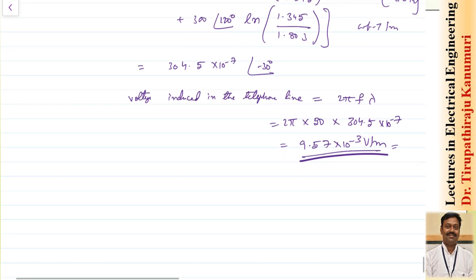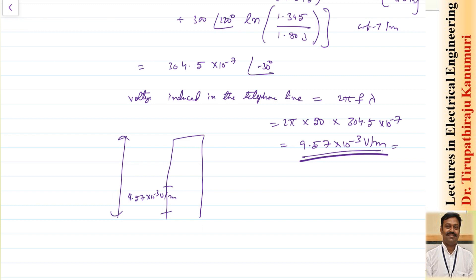This voltage multiplied by the length of your line gives the total voltage induced due to electromagnetic or magnetic effect. This voltage divided by the impedance of the communication line loop gives a current — this interference current adds to the signal current passing in the communication channel, so your signal gets distorted due to the electromagnetic effect.